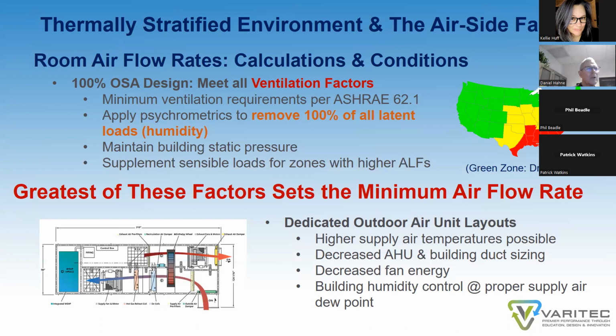Dedicated outdoor air units, however, need to be laid out a little differently. They need to be laid out so they can provide a high enough leaving air temperature of 62 to 68 degrees while also dehumidifying the air adequately. So how do you do that? Well, the air off the cooling coil has to see a low enough temperature to create the dew point depression necessary to control building humidity. And that's an easy enough calculation to do.